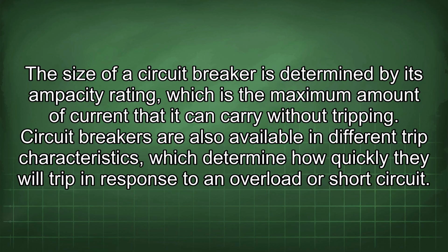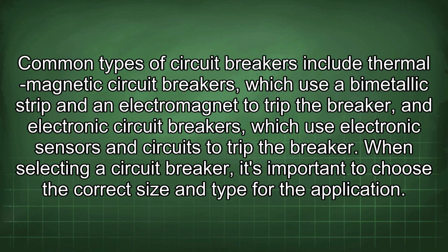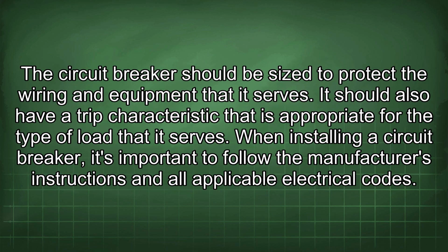Circuit breakers are also available in different trip characteristics, which determine how quickly they will trip in response to an overload or short circuit. Common types of circuit breakers include thermal-magnetic circuit breakers, which use a bimetallic strip and an electromagnet to trip the breaker, and electronic circuit breakers, which use electronic sensors and circuits to trip the breaker. When selecting a circuit breaker, it's important to choose the correct size and type for the application. The circuit breaker should be sized to protect the wiring and equipment that it serves. It should also have a trip characteristic that is appropriate for the type of load that it serves.